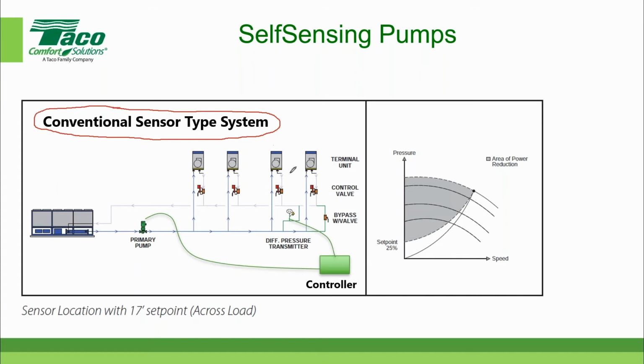Well, that means that in this very, very simplified system we have a differential pressure transmitter. We're actually measuring the pressure differential across the most remote part of the system. And we're sending that information hardwired over to a controller. And that controller has some kind of control logic. In this case, it's saying, look, I want to have a pressure differential at the differential pressure transmitter location, have a set point down here of 17 feet.